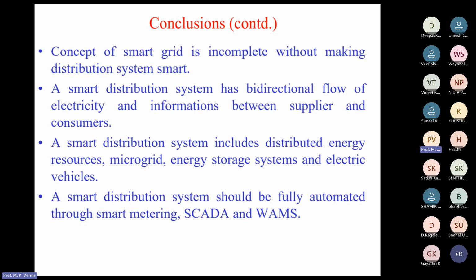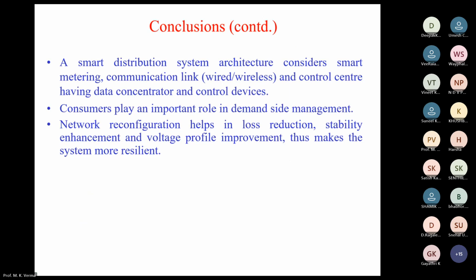So smart grid is incomplete without making the distribution system smart, and a smart distribution system has bidirectional capacity and information exchange between supply and consumers. A smart distribution system consists of distributed energy sources, microgrid, energy storage systems, and electric vehicles, and it has full automation through a smart metering scheme, SCADA and AMI. The communication protocol should be either wired or wireless. A smart distribution system has an architecture consisting of smart metering and communication links, and a control center having data concentrator and control devices.